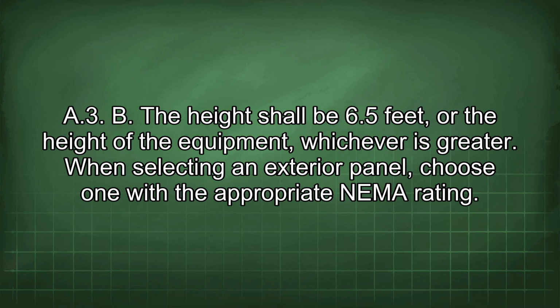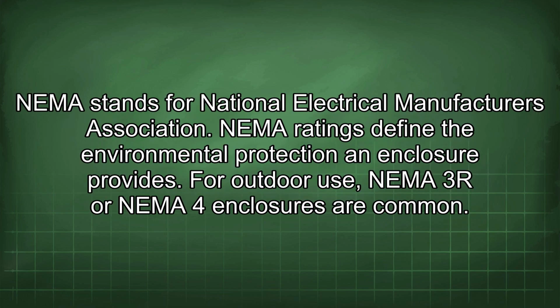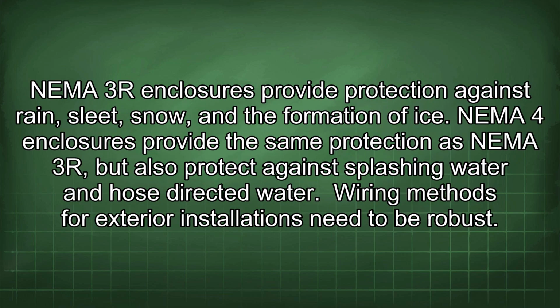When selecting an exterior panel, choose one with the appropriate NEMA rating. NEMA stands for National Electrical Manufacturers Association. NEMA ratings define the environmental protection an enclosure provides. For outdoor use, NEMA 3R or NEMA 4 enclosures are common. NEMA 3R enclosures provide protection against rain, sleet, snow, and the formation of ice. NEMA 4 enclosures provide the same protection as NEMA 3R, but also protect against splashing water and hose-directed water.